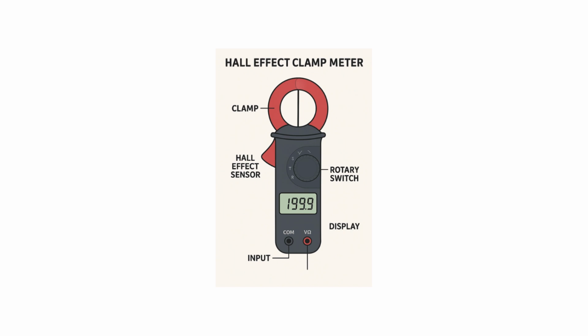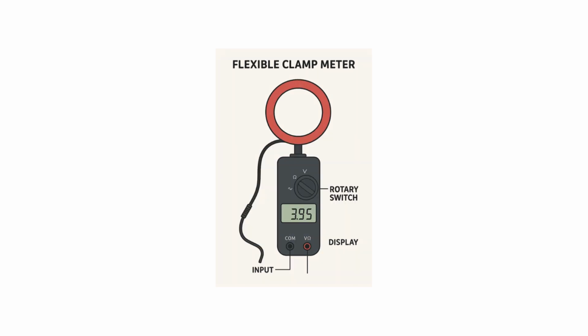The diagram below is for a Hall effect clamp meter. It is very similar to the one of the CT clamp meter, as both have an iron core. The only difference is that the Hall effect has a Hall effect sensor. The parts are clamps, display screen and the dial or rotary switch. The diagram below is for a flexible clamp meter. This is different from both Hall effect and CT clamp meters as they don't have an iron core. It uses a helix-shaped coil. The parts are clamps, display screen and the dial or rotary switch.